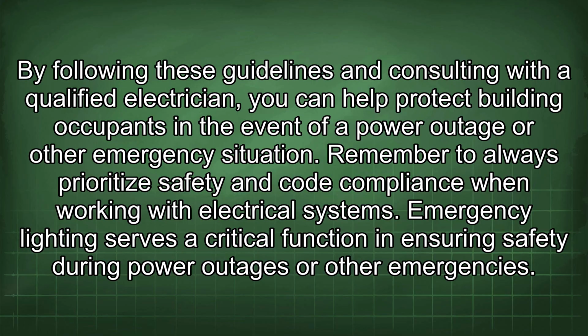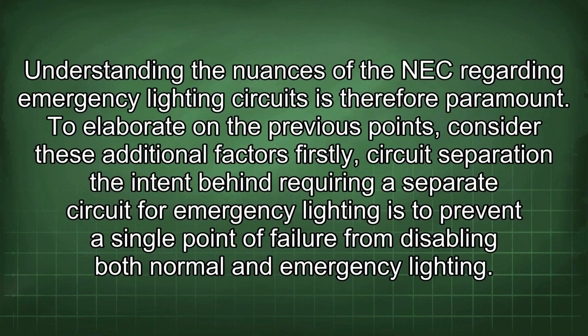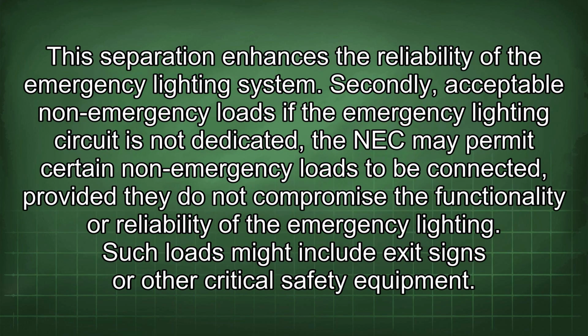Emergency lighting serves a critical function in ensuring safety during power outages or other emergencies. Understanding the nuances of the NEC regarding emergency lighting circuits is therefore paramount. To elaborate on the previous points, consider these additional factors. Firstly, circuit separation. The intent behind requiring a separate circuit for emergency lighting is to prevent a single point of failure from disabling both normal and emergency lighting. This separation enhances the reliability of the emergency lighting system.